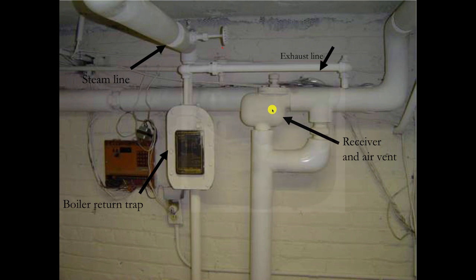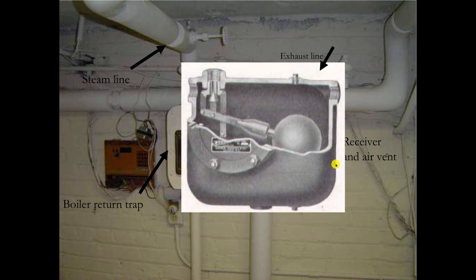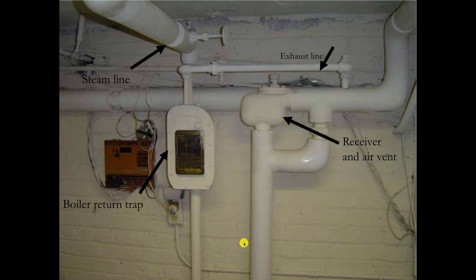The receiver and air vent on the inside looks like this. What we have here is just a float valve, like a ball cock in a toilet. Your vent screws in here, and this float is normally down. Venting goes through there and comes down here. The only time this would go up is if water somehow managed to come up this line, because we don't want spillage. The only way water could come up this line would be if — in coal-fire days — somebody left the ash pit door open, the fire flared up, you had too much heat and too much pressure, and water backed out of the boiler. So if this is there and it's fine, leave it alone. Don't change any of this.